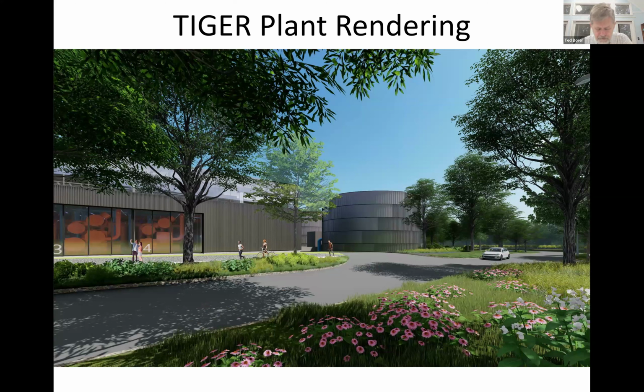This is a rendering. If you've been on Fitzrandolph Road across from the stadium parking, you'll see the heat pump plant on the left and the thermal storage tanks. The cold one is closer to us, and just beyond the trees between the front tank and the plant you can see the hot thermal storage tank. The cold storage temperature is about 41 degrees Fahrenheit, much cooler than you'd want your office on a hot sunny day. The hot one is about 120, maybe 140 degrees, hotter than you'd want your office or shower. So there's some thermal leverage, or potential energy, that can be lost in the transition from the tanks or the heat pump plant out to the buildings.